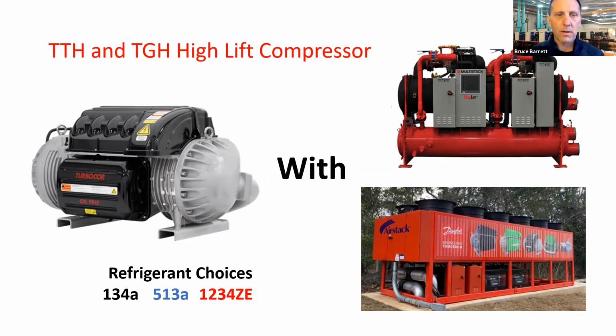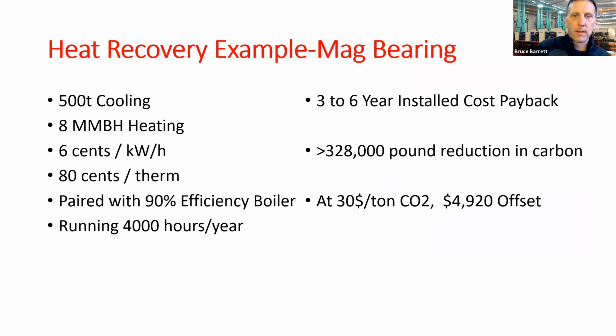This Danfoss Turbocor compressor is offered in 134A, 513A with a click of a button in our selection program. And we're also offering through special engineering 1234ZE for near zero GWP refrigerant offerings. So just giving a quick example, 500-ton cooling load with 6 cents a kWh, which is about the rate, 80 cents per therm, 90% efficiency boiler running 4,000 hours. It's about a 3 to 6 year installed cost payback employing the mag bearing technology.